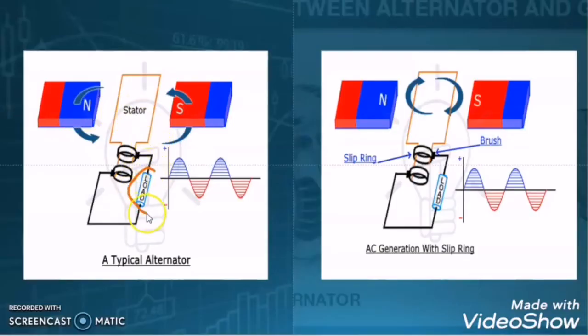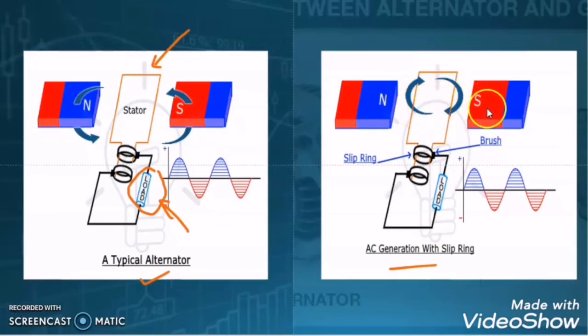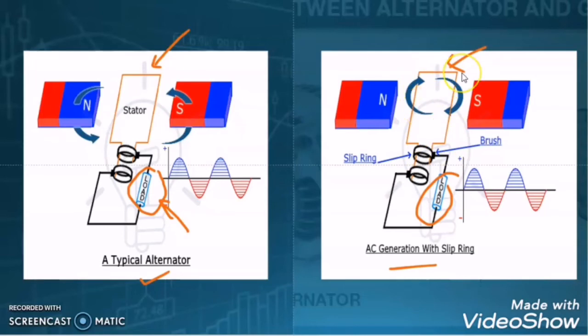As we see, the load is connected with the armature of the alternator which is stationary, and the field is rotating with respect to the armature. So the armature is the stator because it is not moving — in case of an alternator, the load is connected with the stator and we are getting power supply to the load via the stator. But in case of a generator, the armature winding is spinning with respect to the field winding, and the load is connected to the armature which is rotating — so we are getting power supply to the load through the rotor.